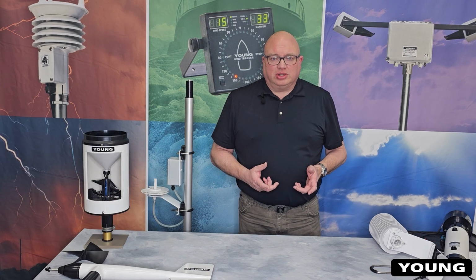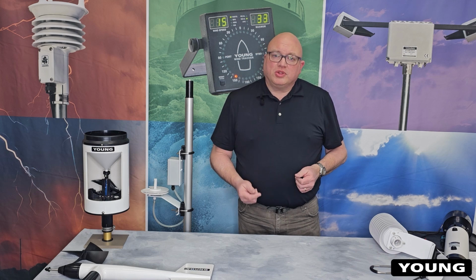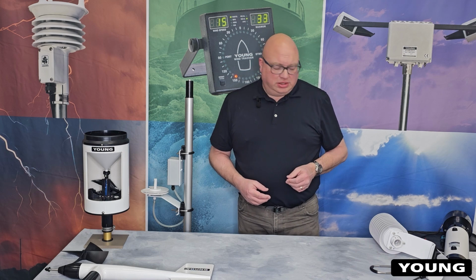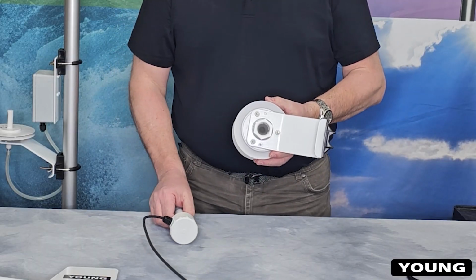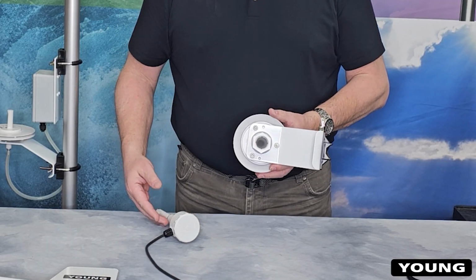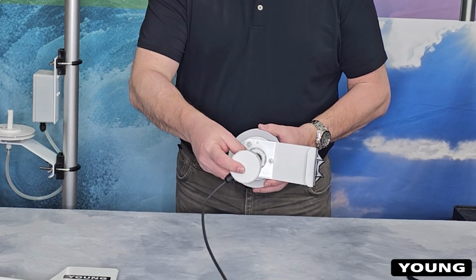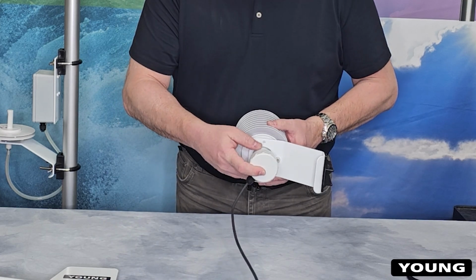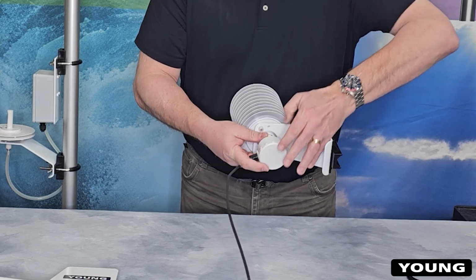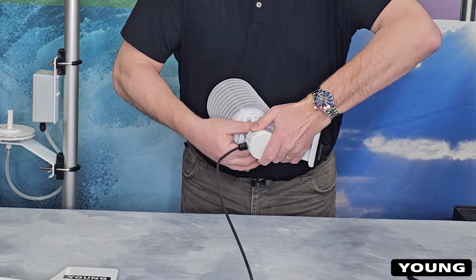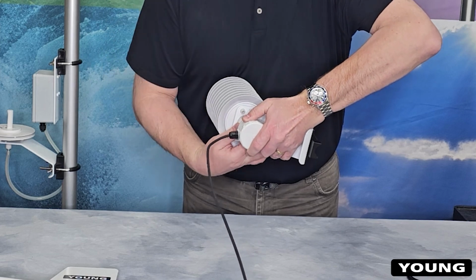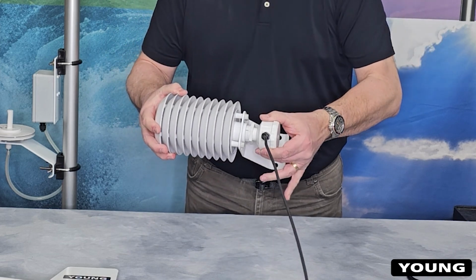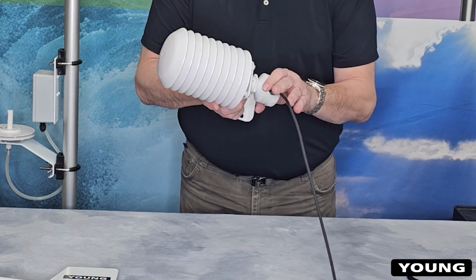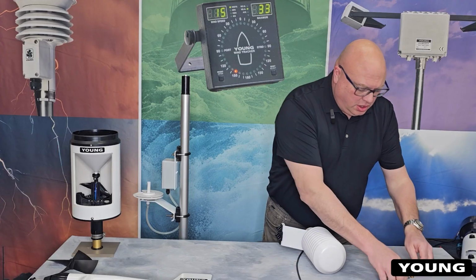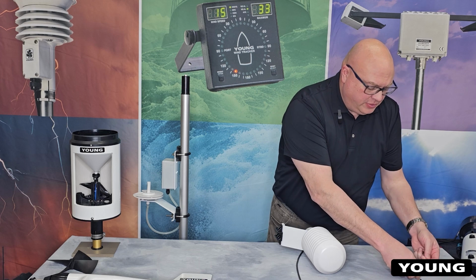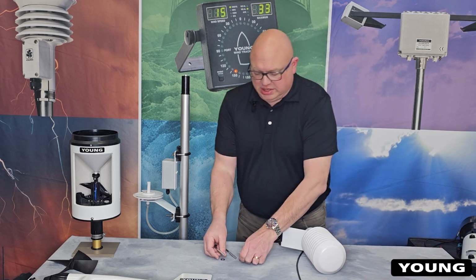The next instrument we're going to install is a temperature and relative humidity probe in the solar radiation shield and install it on the mast. Our solar radiation shield comes with an adapter that allows you to easily install the temperature humidity probe. Simply insert it into the adapter and tighten it to secure it. Please note you do not need to over tighten it, just snug it up. Once you have it installed, use the provided U-bolt and hardware to clamp it to the mast.